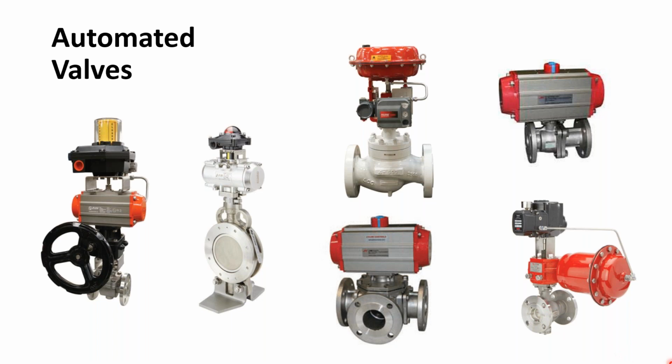So segmented valves can typically handle 85 to 90% of most applications, instead of a traditional globe control valve, which can be very costly. So depending on the working pressure and service conditions, because we can only do so much here, we do have an anti-cavitation trim that we put in this valve, but it's limited to maximum 400 PSI differential, whereas we can go all the way up to 4,000 PSI, and we can have all kinds of unlimited options in our valve for those types of trims. So segmented is a half a ball, and it's been around for a long time now, and it works extremely well. So it's part of our control valve lineup.